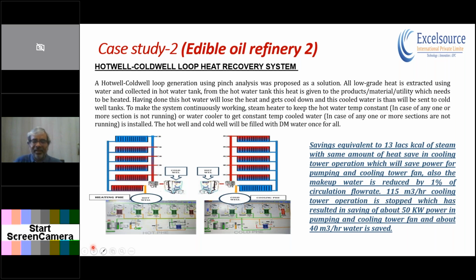So the second thing that is happening in the industry by doing this pinch technique, one more advantage achieved by the industry, is that the investment in the steam generation unit, the boiler, is delayed or maybe even avoided in the future, because this extra steam which is available from the boiler can be used for any potential expansion which is going to come in the future. So they are avoiding the installation of capital equipment, which will save the capital cost, and the carbon footprint is also optimized.